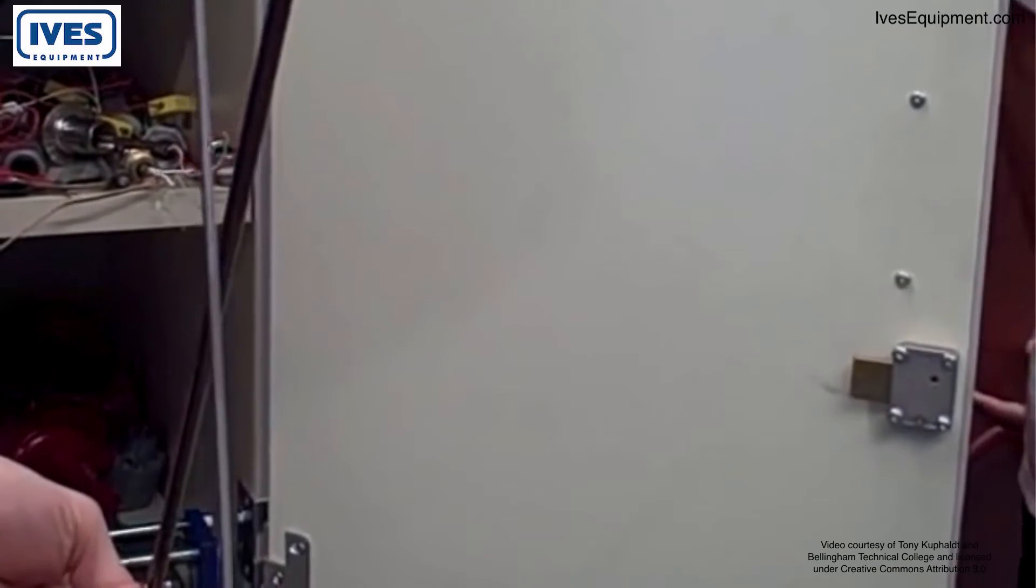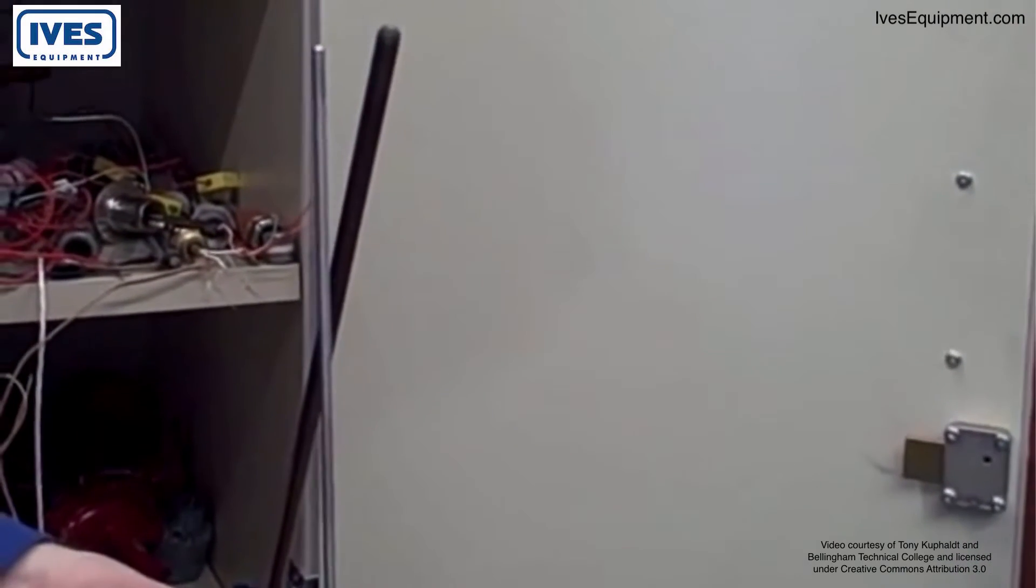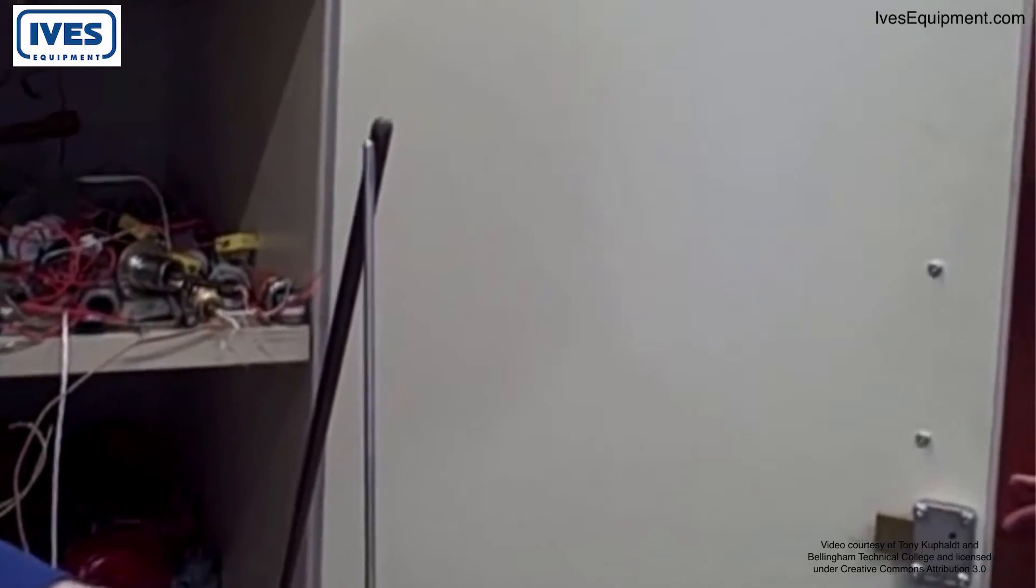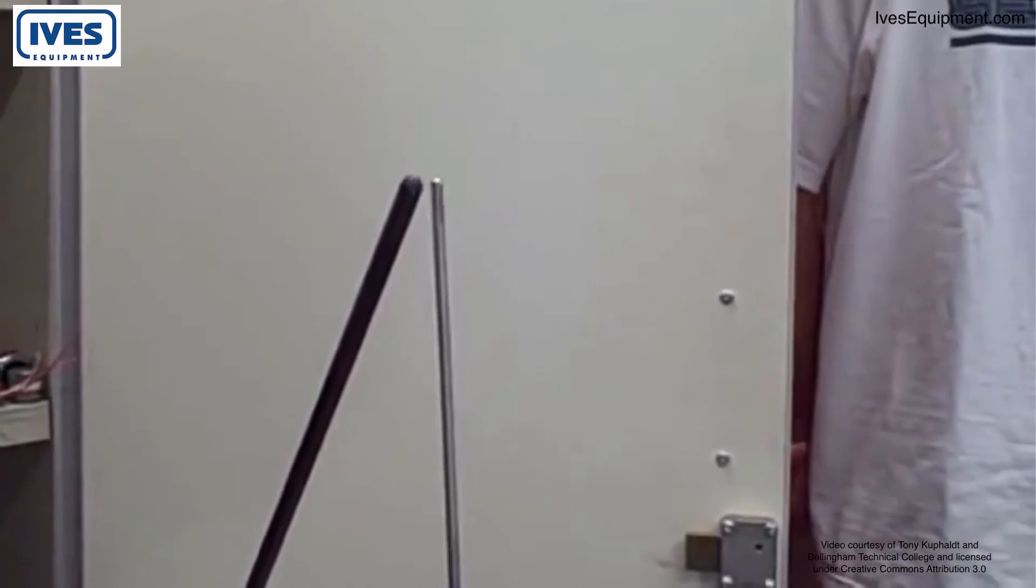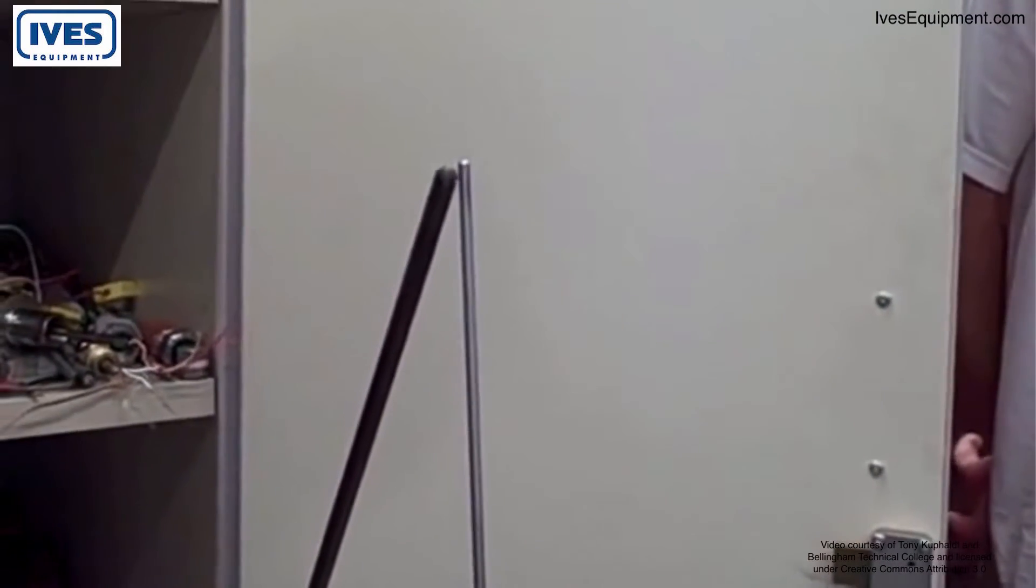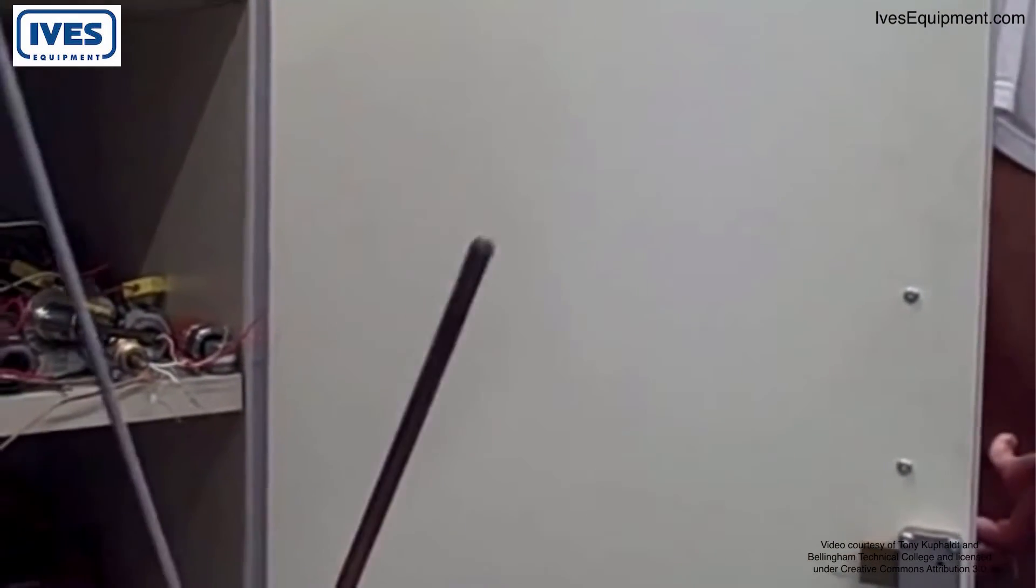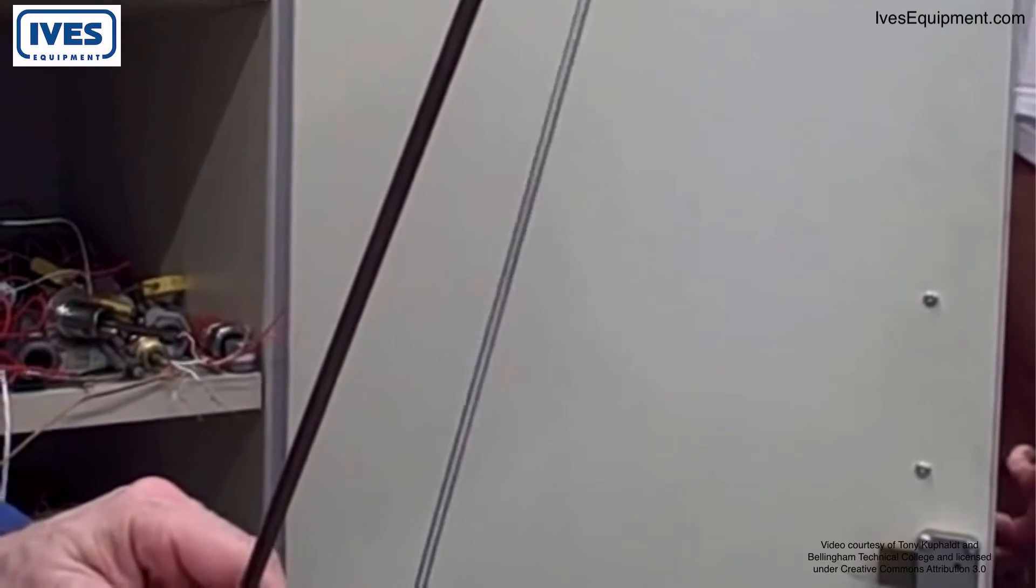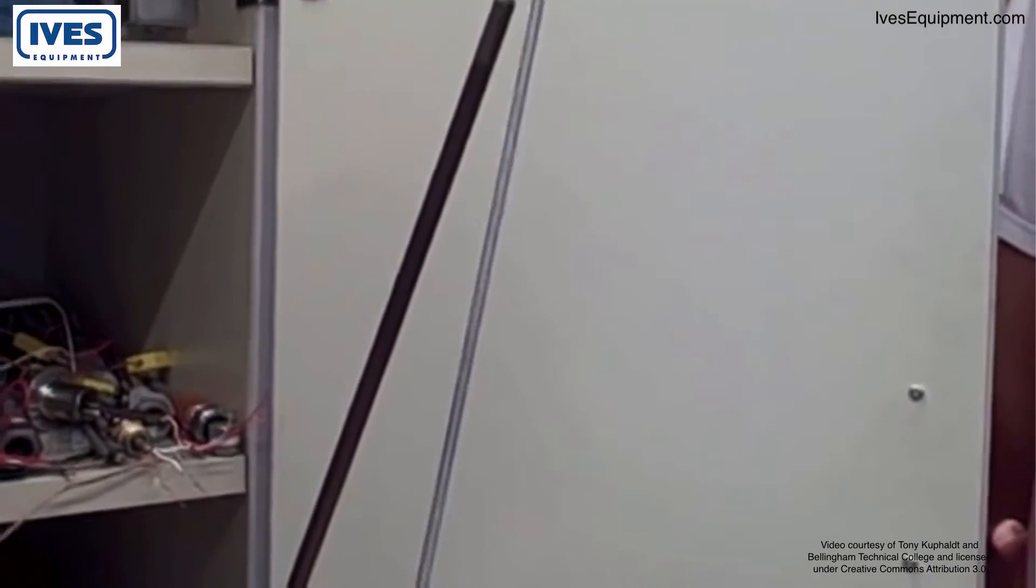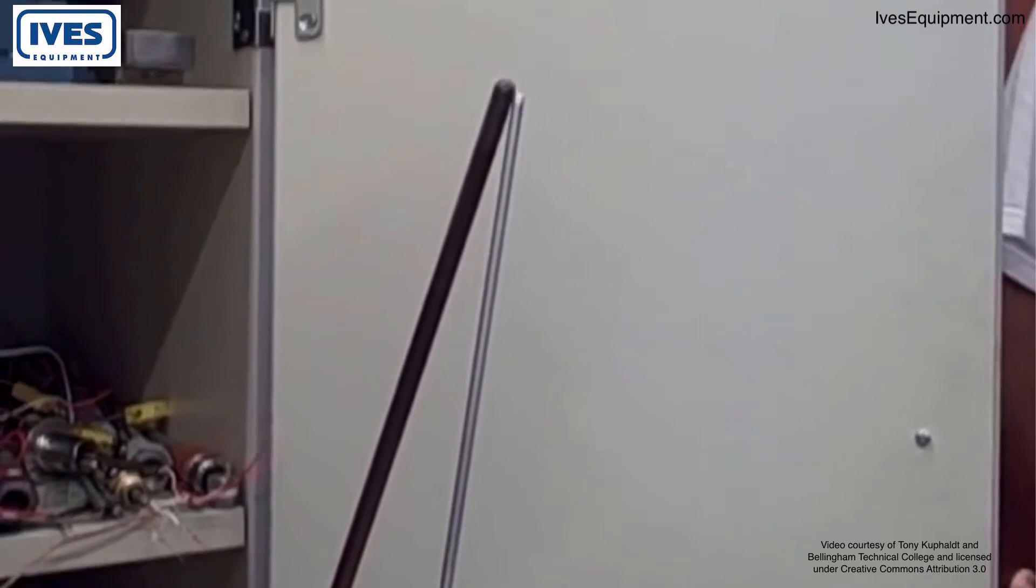However, we know that in both these cases they are not an exposed tip. An exposed tip would be obvious. You would see the thermocouple wires jut out with a little blob at the end where they're welded together. You don't see that here. These are both covered tips. They're sheathed by stainless steel. That protects them from the ravages of the process.